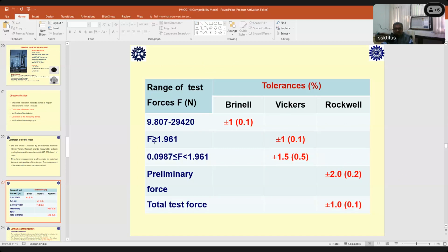For Vickers, normally we talk about micro Vickers and the normal one. Micro Vickers means when the force is less than a certain value, that is 1.961 Newton, and then the application of the force can be plus minus 0.1 in the case of the testing machine, and in the case of the calibration machine it's plus minus 0.1%. And if the application of force is less than that, for the micro Vickers, then the tolerance is a little higher, because with small forces, definitely the uncertainty will be high. So it is 1.5 for the testing machine. Again, for the calibration machine, it has to be very strict. It has to be 0.5%.